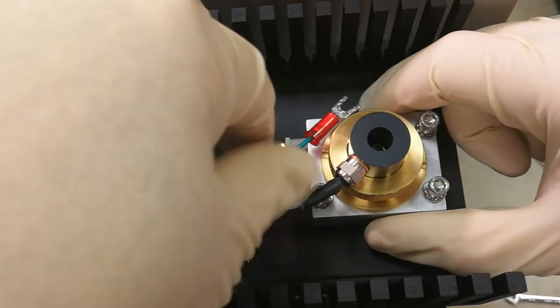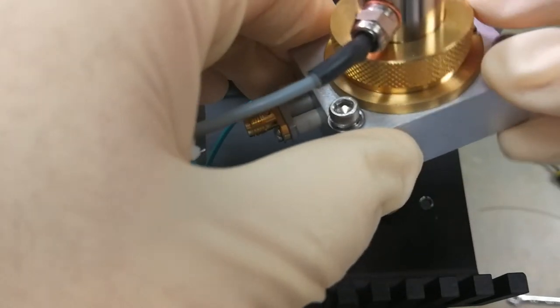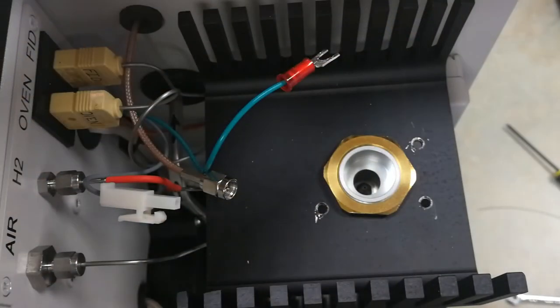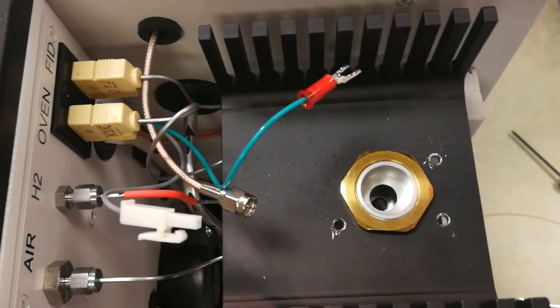Remove your FID collector, the whole assembly. Set it to the side. You can see where your jet is.